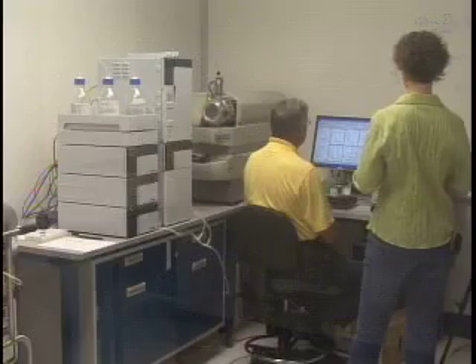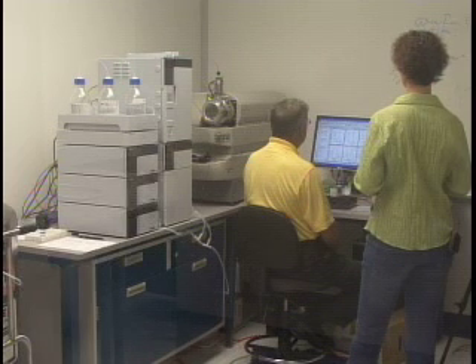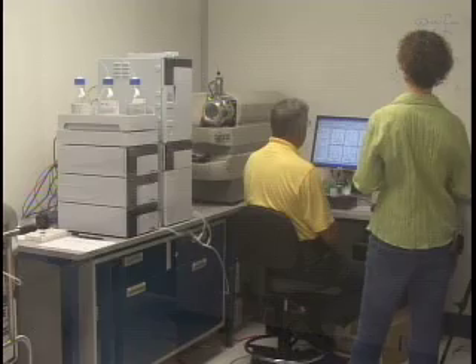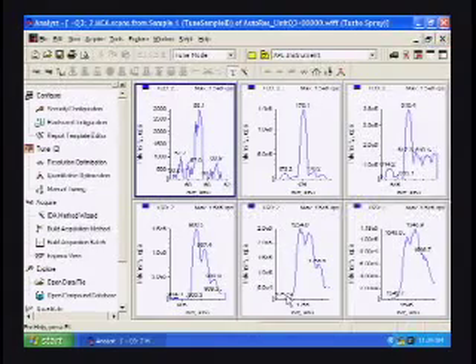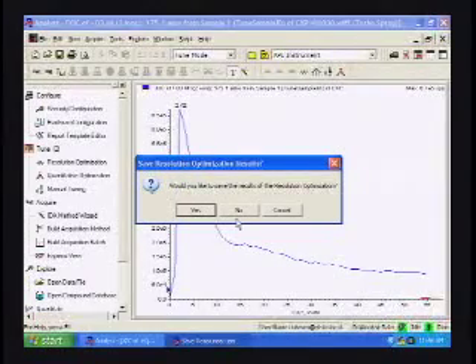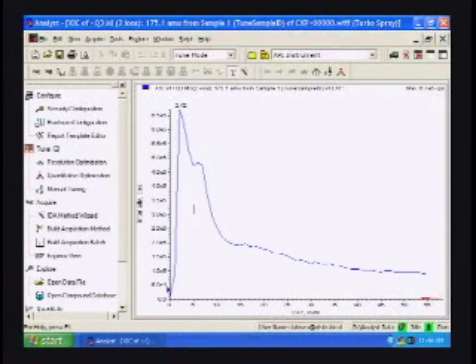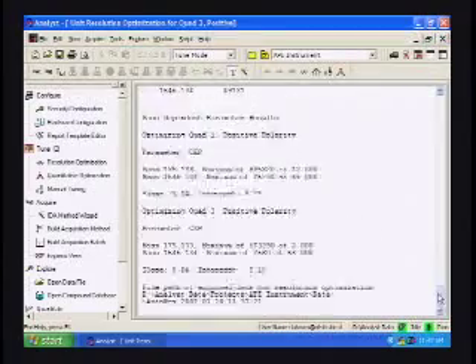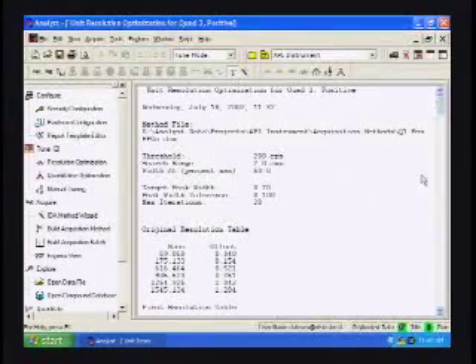So you can tell this is about the third time it's done Q1, so now it's moved on to the Q3 mode. Okay, at this point the resolution optimization is complete, so we'll click OK. And it asks if we want to save the results of the resolution optimization. The answer to that is yes. And the entire report is here. And typically we save this report because it shows the tables and what was changed.